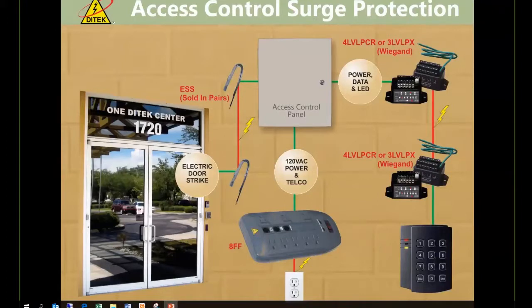On the end for your readers, we do offer the power data. We offer the 4LV-LPCR, which is a 4-pair device protecting LED, as well as low volt data in 12 and a 24 volt pair as well. The 3LV-LPX is a standard device we use on Wiegand protocol. All the data and power is at 12 to 14 volt, and we're showing there that you're protecting not only the access control panel but the remote location for the reader as well.